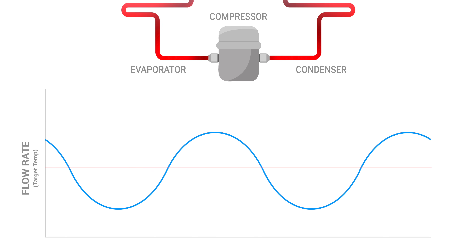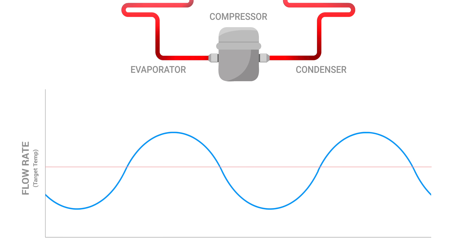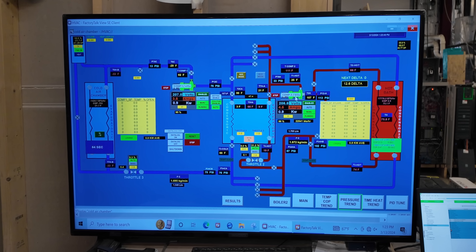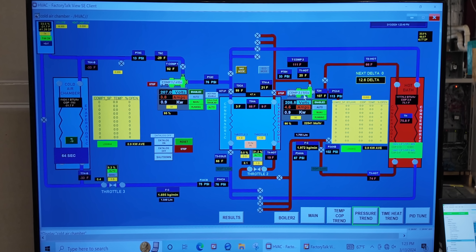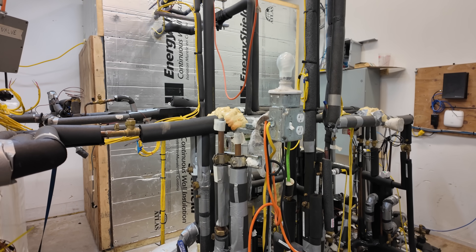Then how do heat pumps avoid this? The safest method is to dial up the temperature of the entire cycle so the lowest portion of the sine wave is almost always above the working fluid's preferred temperature. However, turning up the heat on a system like this costs extra energy, equating to a poor COP and energy efficiency. The tighter that you can dial in the sine wave and the control systems around it, the less of an offset you'll need, which means a more performant system. That's exactly what the Fluid team says they've done. They've developed a very tight control software that's closely managing the superheat of the vapor, limiting it to a single degree of variance. This solves the superheat issue without having to burn extra energy. Using software to optimize your HVAC system like this has been around since the 80s, but it contributes to Fluid's great performance and opens the door to some neat tricks.